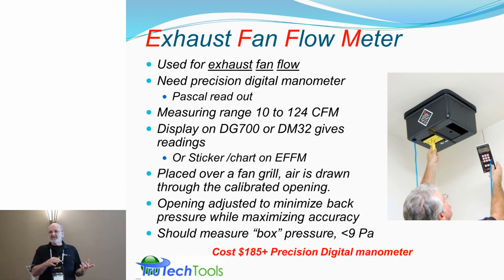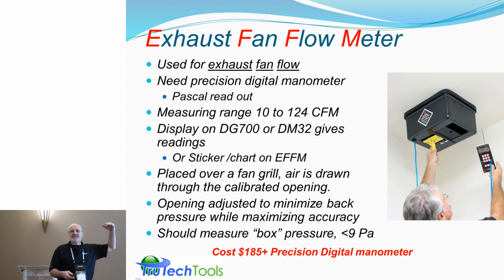If you choose not to use one of their products, you can actually use it with anything that has a good Pascal readout. You place it over the fan grill, air is drawn through this calibrated opening, and the meter itself tells you the CFM. We talked about this before: this is a bulk measurement on exhaust or returns. One thing, you slap it on, you get a good measure.